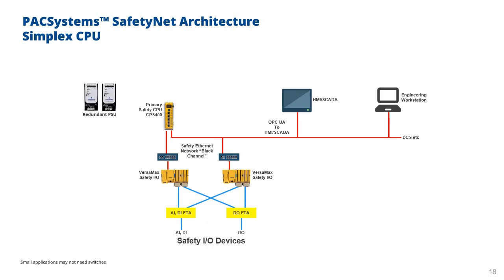I've put here on redundant power supplies, but again, you might not need redundant power supplies. A simplex power supply might work, but of course, from an availability point of view, if a single power supply fails, then the whole system shuts down and your plant trips. So redundant PSUs are not mandatory, but are recommended. HMI SCADA is optional using OPCUA communications. Engineering workstation, that's your PAC Machine Edition software, and there will be an optional interface to DCS using either OPCUA or Modbus TCP communications. Quite straightforward. With that one though, you're limited with Versamax to 8 I/O modules, so that would limit how much I/O you could actually have in this system. But for a small system, this would be entirely feasible to implement at a relatively low price.